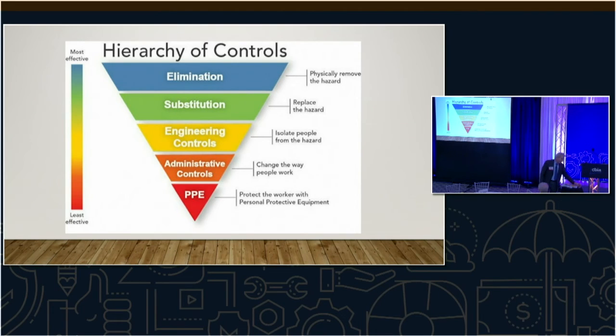Hopefully they say with a meter. I said, well, that's considered live work. Well, what do you mean? Well, you're verifying to see if there's voltage there, so there could be voltage there. So even though it's lower risk because you shut it off and now you're just verifying, you're bringing the risk down really, really low, but the severity is really, really up, because you touch something and there are examples.